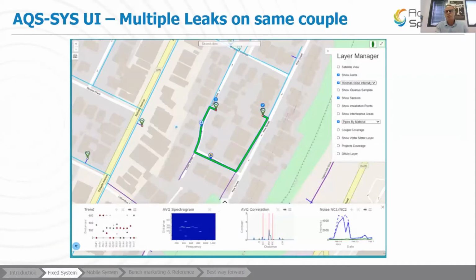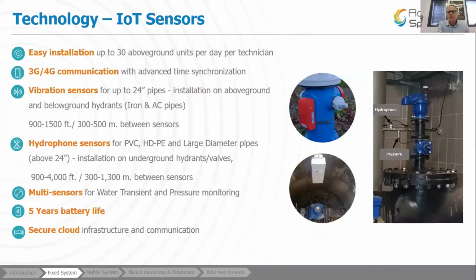We just introduced a new version a couple of weeks ago that is able to trace 2 leaks, even 3, between 2 sensors. It's really cutting-edge, a very innovative feature — if there's a pump in the system masking the leaks, we're able to hear both the pump and the leak. A very strong feature. In terms of technology, we don't have any limitations.